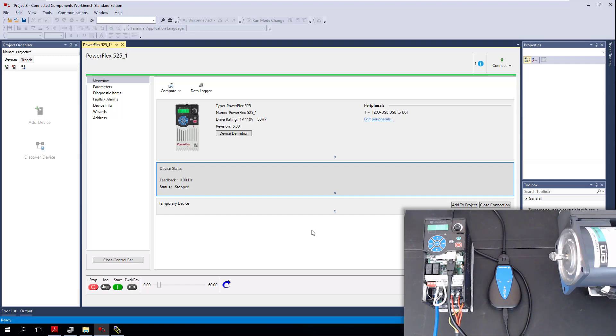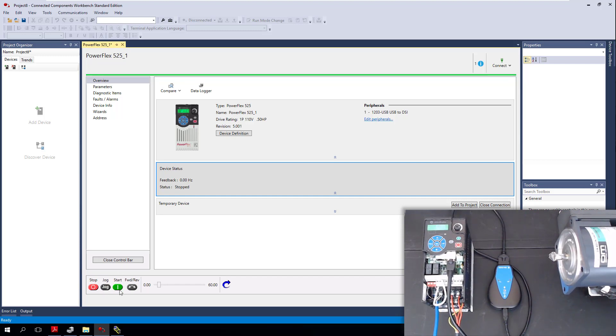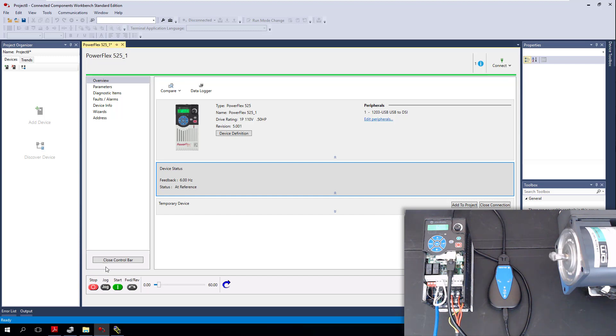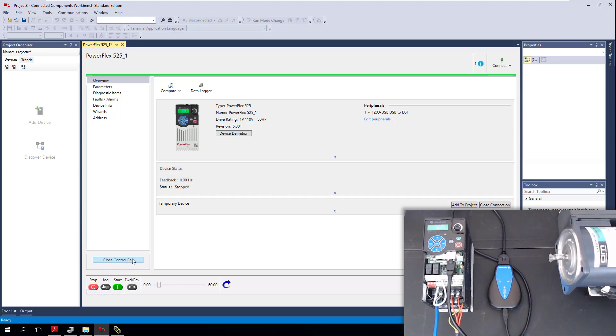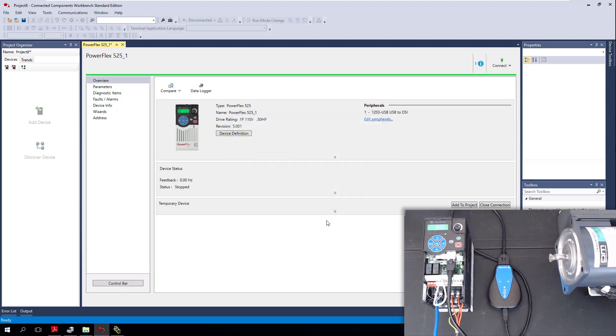In this video, we're going to set up our PowerFlex 525 through Connected Components Workbench using a 1203 USB, and then communicate to it so we can use the control bar to start our actual motor and control it to do a commissioning test. I'm going to show you how to set everything up from your RSLinx driver, from your actual driver for your 1203 USB to getting a successful upload, then controlling your motor through the control bar, all in under 10 minutes.